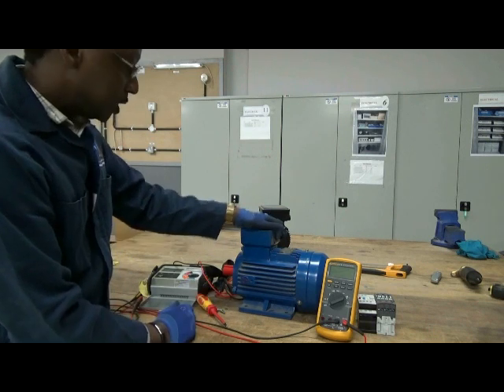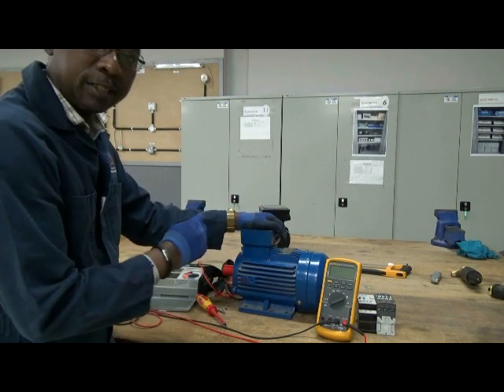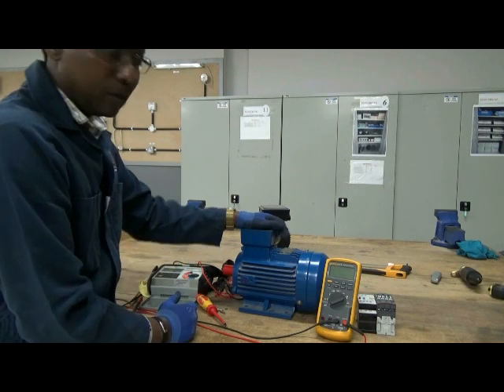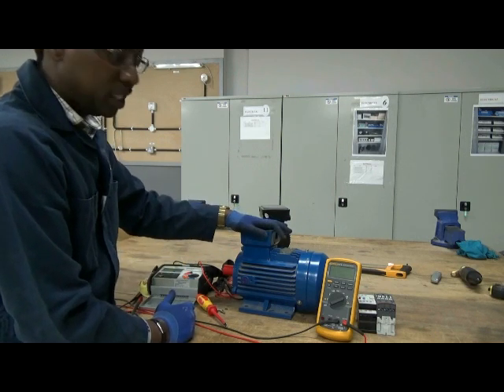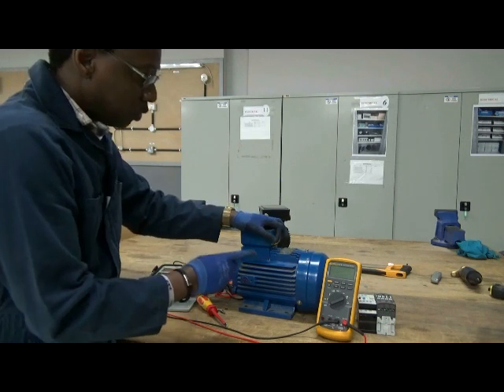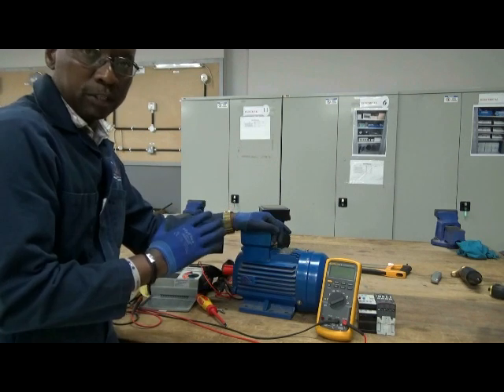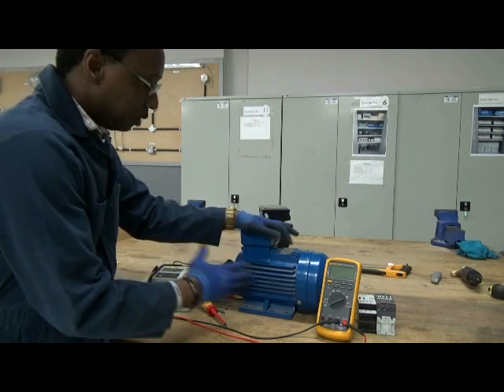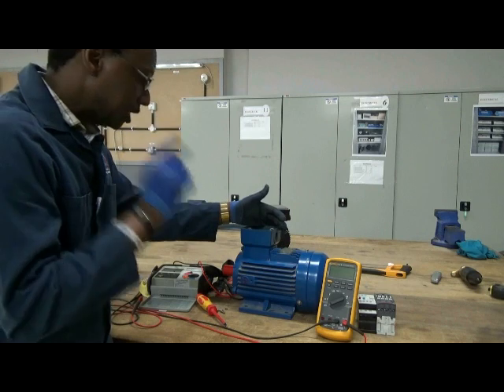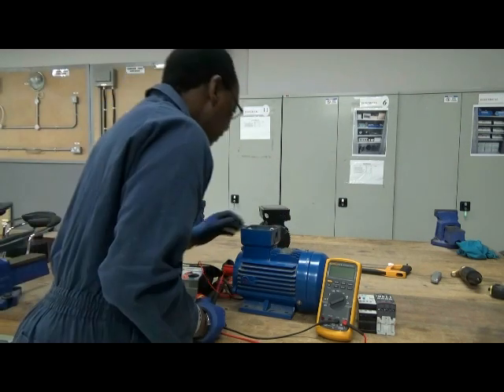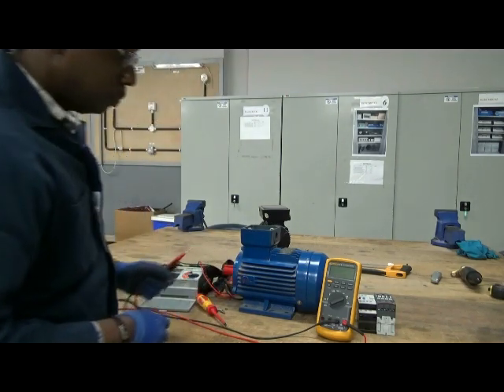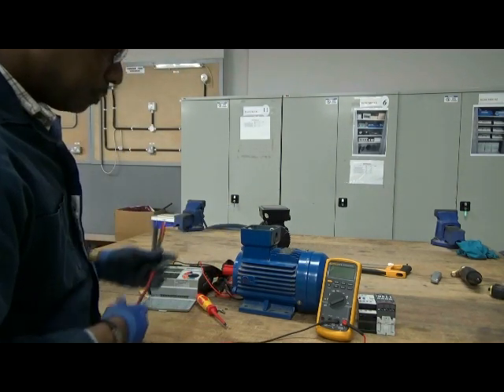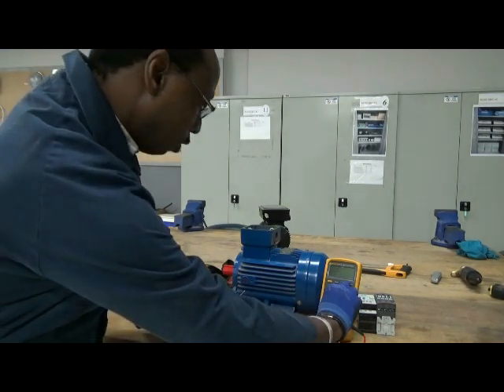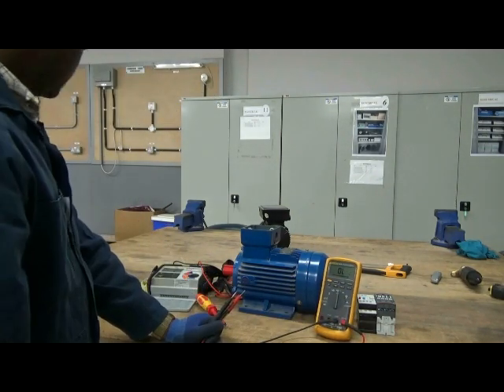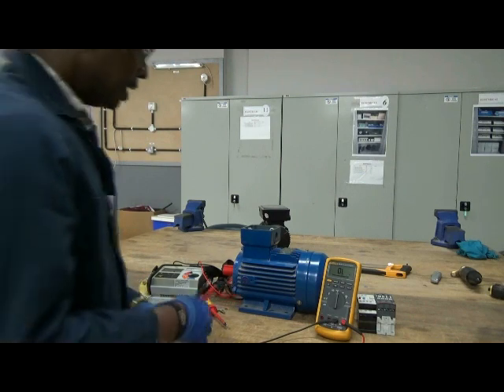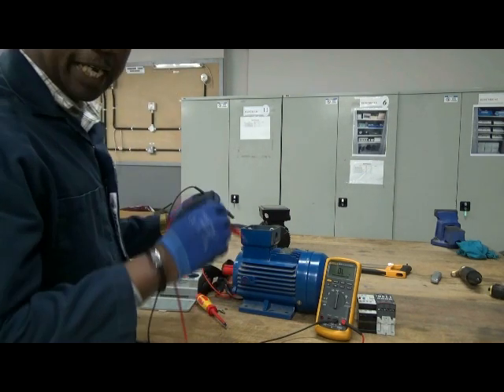And secondly, to see that the windings have got the same resistance, because this is a three-phase load, which means we should have the resistance of the windings equal throughout. First winding, second winding, third winding, we should have the same value of resistance throughout. So what I'm going to do here now is to switch on the multimeter. I'll select the ohm scale so that I can measure the resistance of each and every winding. First of all, I have to identify the beginning and the end of the winding.